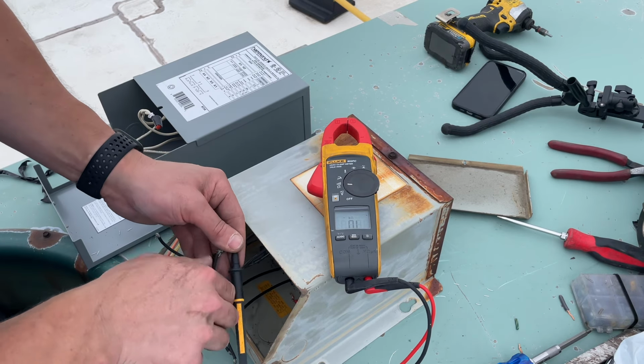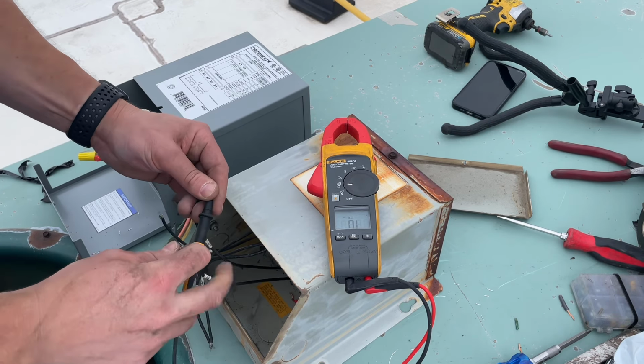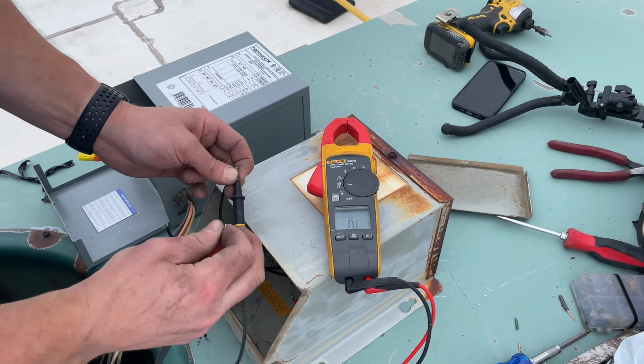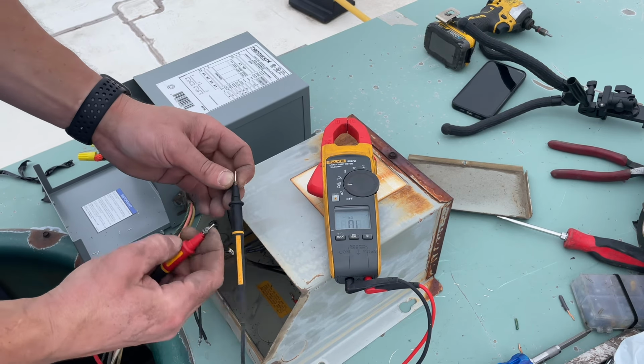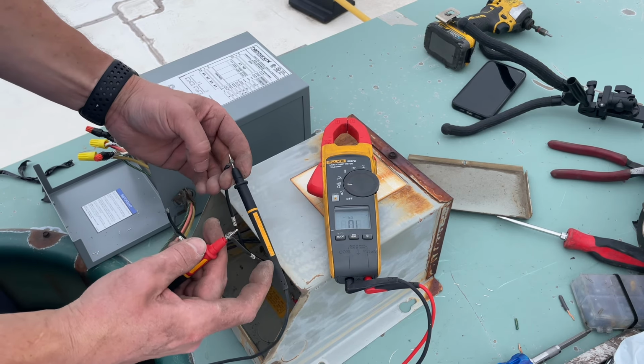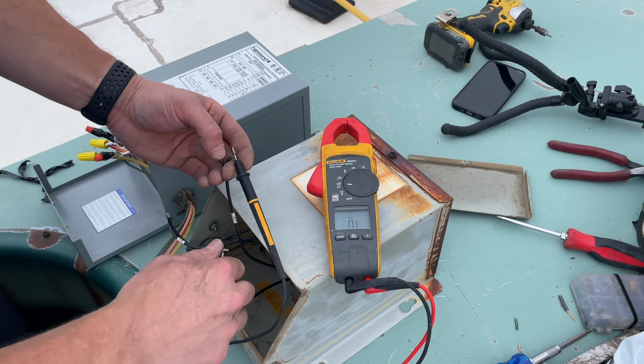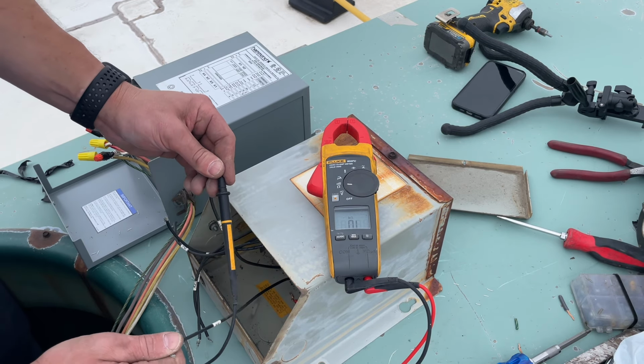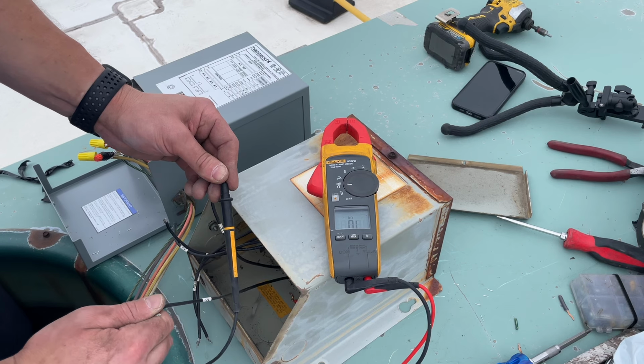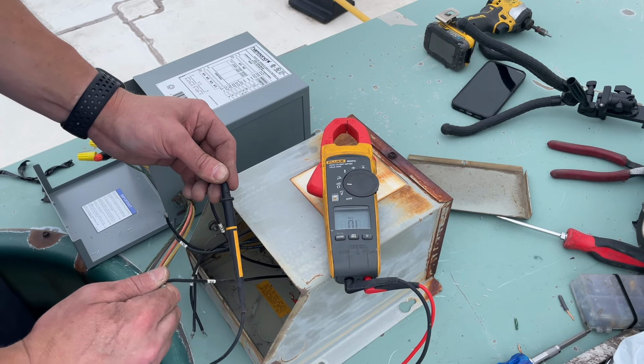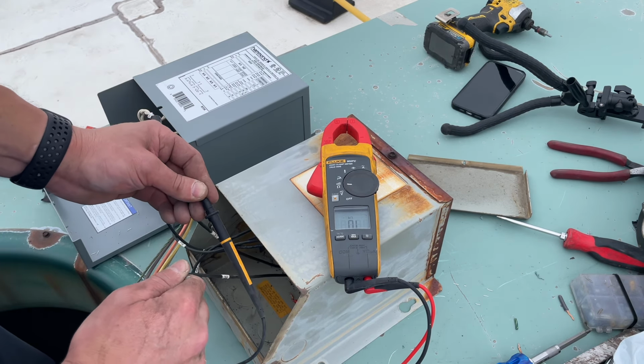We have 2.6 ohms resistance across the primary side of the transformer. Let's do the same thing on the secondary. And we're reading nothing on X4 and X1. I'm on both leads, X4 and 1, and we have outer limits. So it's open — the windings are burnt up, there's a break in them somewhere. Who knows, but this transformer is trash.